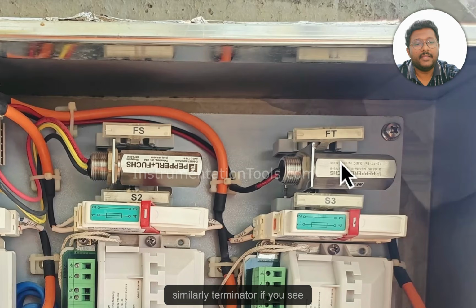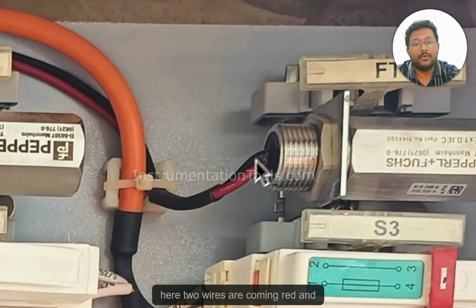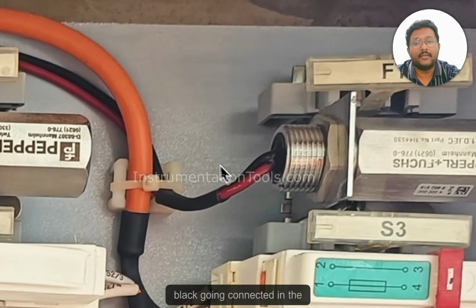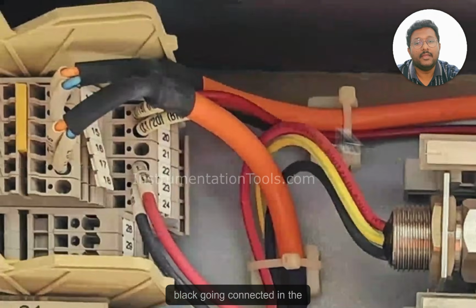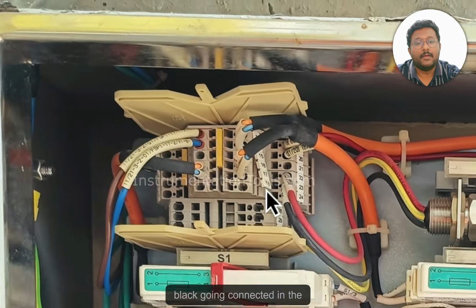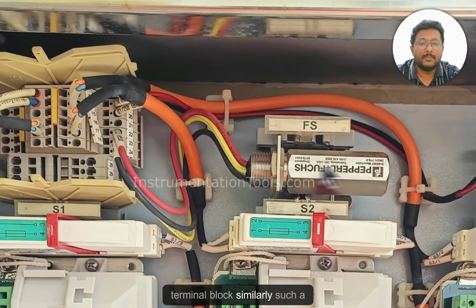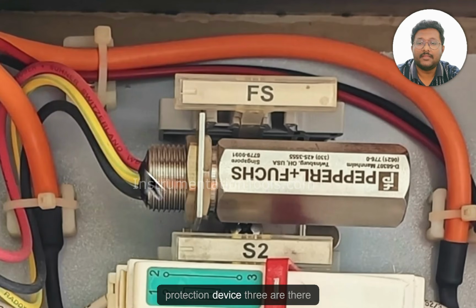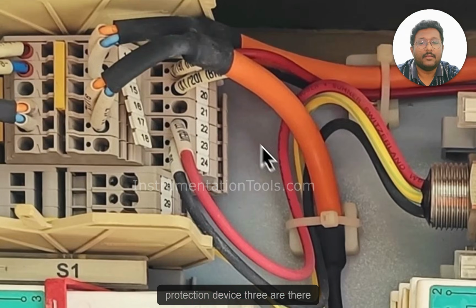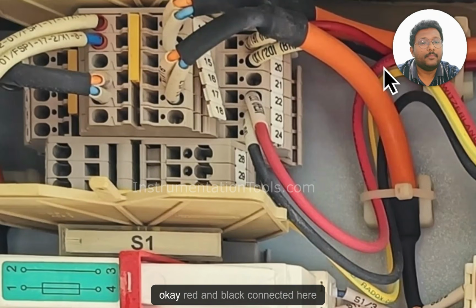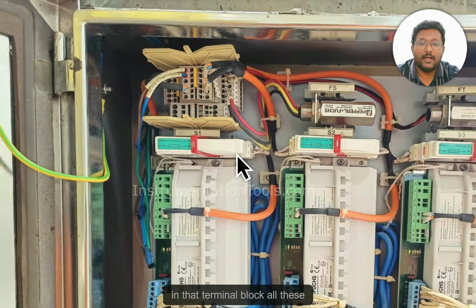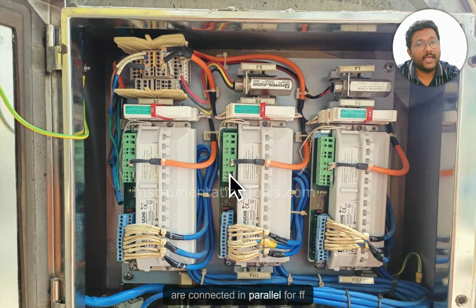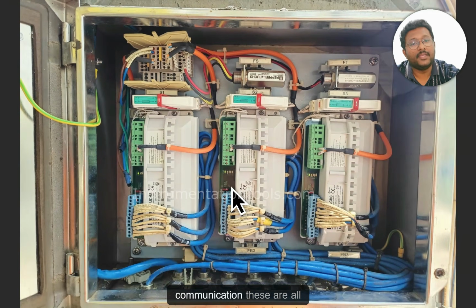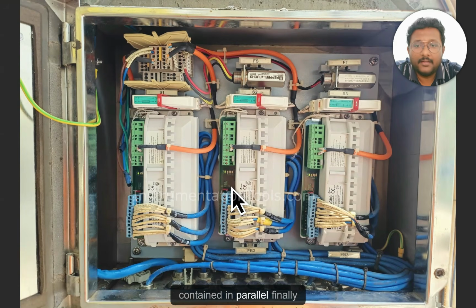Similarly, the terminator, if you see here, two wires are coming, red and black, connected in the terminal block. Similarly, the surge protection device, three are there. Red and black are connected here in the terminal block. All these are connected in parallel for FF communication.